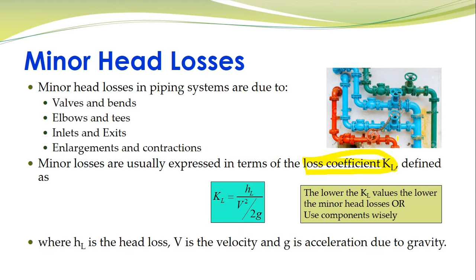And generally minor head losses are studied in terms of the loss coefficient KL. So KL is given as HL upon V squared upon 2G. HL is the head loss, V is your velocity and G is your acceleration due to gravity. And as a rule of thumb, the lower the KL values, the lower the minor head losses. Or what we can do is, instead of using so many components in a piping network, we use them wisely. So we choose which components to use and exactly where we want to place them.